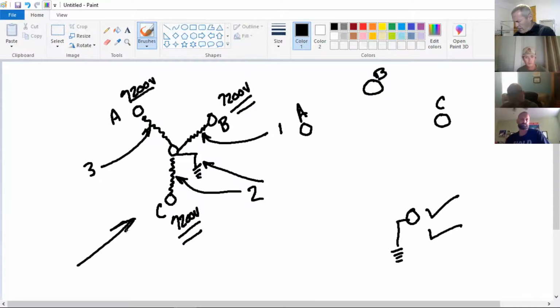Over on the bottom of page 303 - I gave you this early in math, but now we're finally getting to it in the book. Second paragraph: in a Y-connected system, the line voltage is higher than the phase voltage by a factor of the square root of 3, which is 1.732. I add the 5 because that's correct and gives a bit more precision. So whenever you take the phase voltage and multiply it by 1.7325, you get the phase-to-phase voltage. Any questions there?